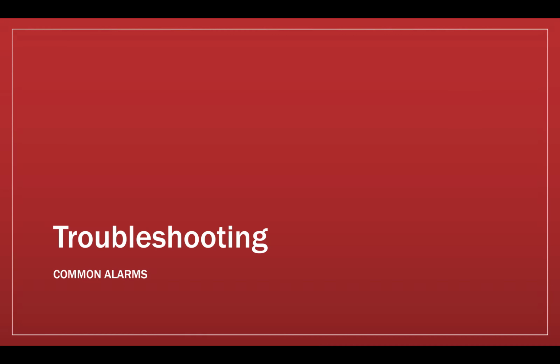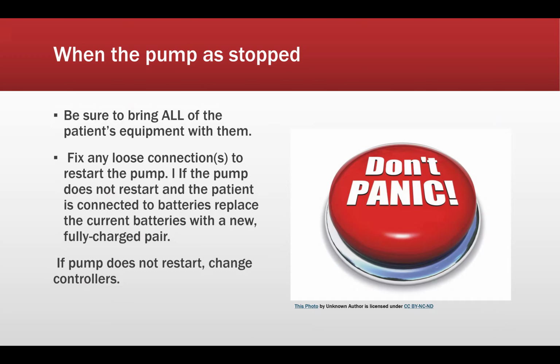So, troubleshooting. This is one of the most common alarms. Again, I really want to push the fact that you need to call that VAD coordinator, because they are going to know this device. We don't see these very often. If the pump is stopped, make sure to bring all of the patient's equipment with them. Fix any loose connections to restart the pump. If the pump doesn't restart and the patient is connected to batteries, replace the current batteries with a new fully charged pair. When changing the batteries out, you don't take both batteries out and change them at the same time, because the pump will stop. We change them one at a time to make sure we still have power going to that pump.